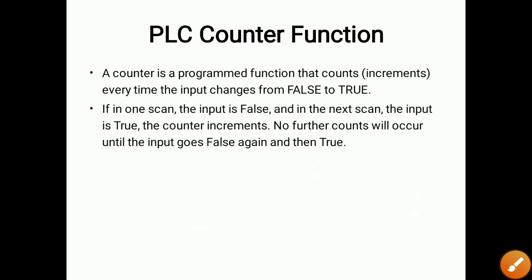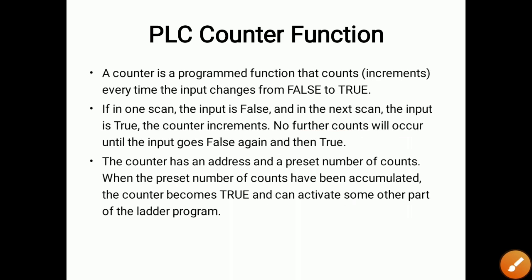Until the input goes false again and then true again, no further count will occur — the key condition is that false must be converted to true. The counter has an address and a preset number of counts. When the preset number of counts have been accumulated, the counter becomes true and can activate some other part of the ladder diagram.